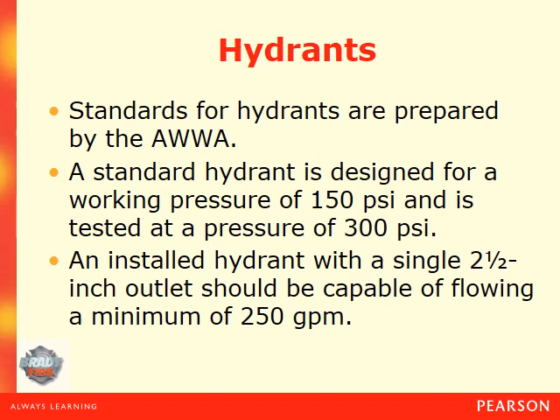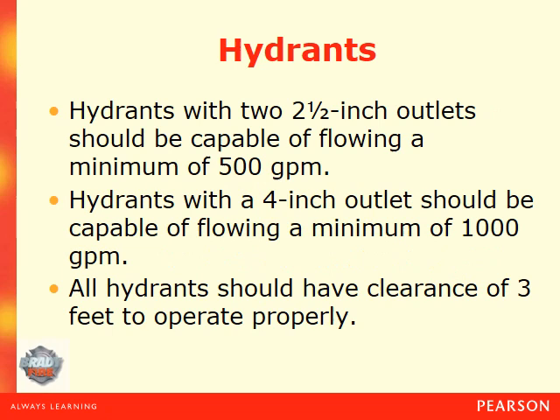Standards for hydrants are prepared by the AWWA. A standard hydrant is designed for a working pressure of 150 PSI and is tested at a pressure of 300 PSI. An installed hydrant with a single 2.5-inch outlet should be capable of flowing at a minimum of 250 gallons per minute. Hydrants with two 2.5-inch outlets should be capable of flowing 500 gallons per minute, and hydrants with a four-inch outlet should be capable of flowing a minimum of 1,000 gallons per minute. All hydrants should have clearance of three feet to operate properly in all directions.